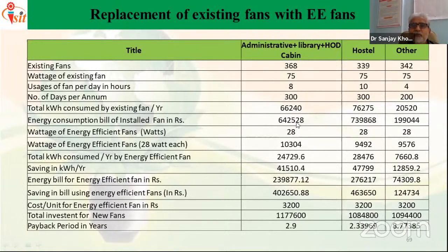Energy consumption bill for the installed fans is 6,42,000. Now we are recommending to replace the 75 watt with 28 watt. So the wattage of the energy efficient fan is this, and the total comes to this much. Total kilowatt hours consumed per year by the energy efficient fan is 24,000. The saving is 41,510 electric units. Energy bill for the energy efficient fan is 2,39,000. Saving in bill using energy efficient fans, this minus this, comes to 4,02,650. Cost of fan we have considered as 3,200. Total investment is 11 lakh, but payback is only 2.9. That means after 3 years, this much is the saving. It is a continuous saving, 4 lakh is the saving.